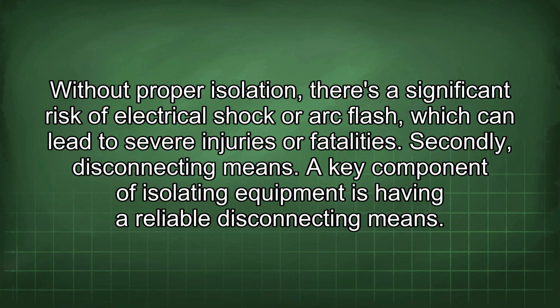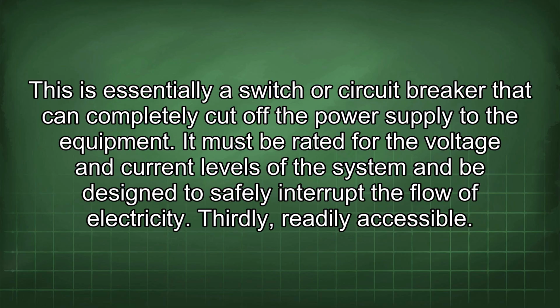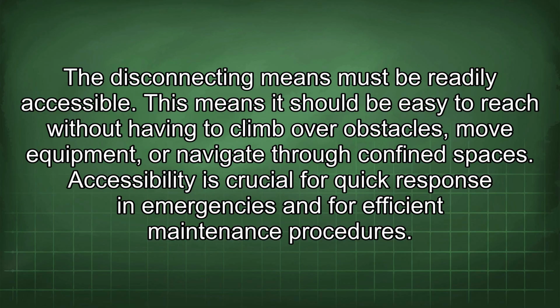Secondly, disconnecting means. A key component of isolating equipment is having a reliable disconnecting means. This is essentially a switch or circuit breaker that can completely cut off the power supply to the equipment. It must be rated for the voltage and current levels of the system and be designed to safely interrupt the flow of electricity. Thirdly, readily accessible. The disconnecting means must be readily accessible. This means it should be easy to reach without having to climb over obstacles, move equipment, or navigate through confined spaces. Accessibility is crucial for quick response in emergencies and for efficient maintenance procedures.